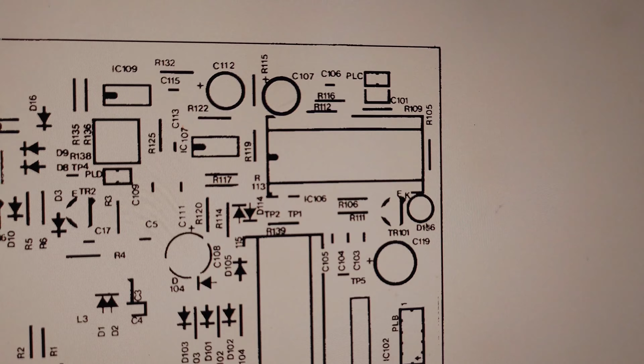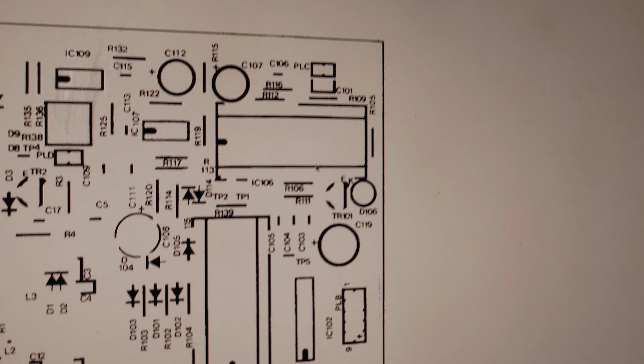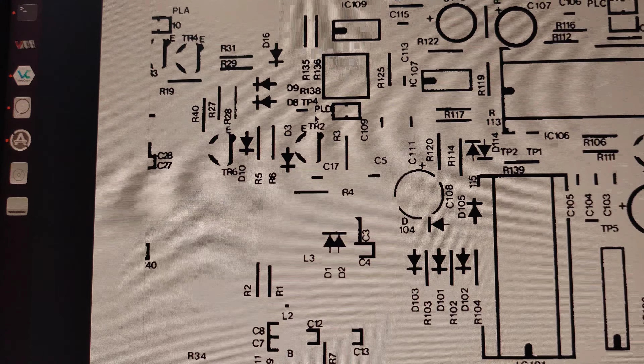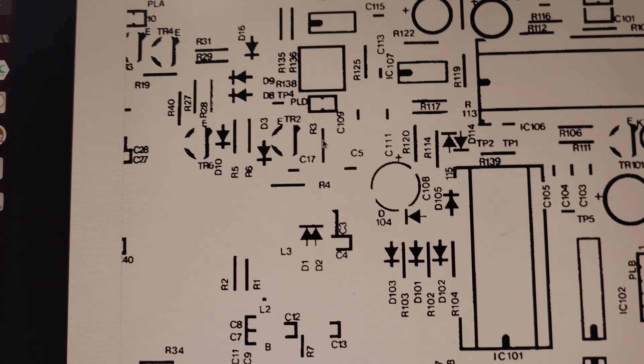But in any case, it has this very useful red LED output, which was telling me that it wasn't locking, which makes sense since the frequency I was getting out of the device was completely wrong. So following the service manual, I was doing some diagnostic testing, which had me hook up to test point 4. And near test point 4, on R3, you have the actual control voltage that's coming out of the PLL and going to the VCO, which is also discrete and external.